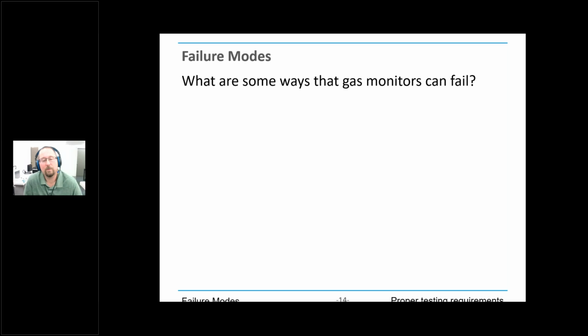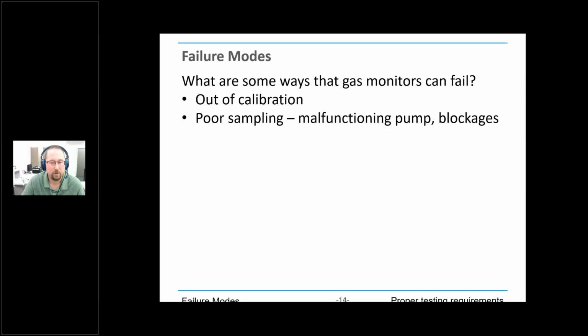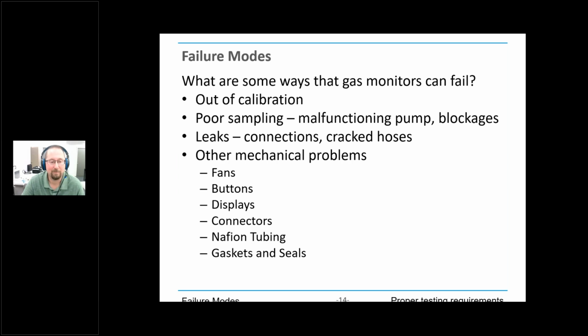And so I'm going to shift to a point here where we start talking about some of the failure modes for gas monitors. They fail in a number of ways. They can be out of calibration. You can have poor sampling. We're going to talk about not each one, but most of these in detail here. You can have leaks in the system, which affect readings. You can have a number of mechanical problems or other things that need replaced or serviced within it. And so let's talk about poor sampling first.